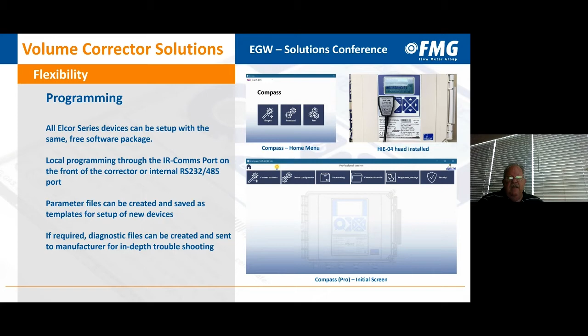Programming. So each corrector, the old ones as well as the new ones today, they require a meter K factor, compressibility calculation method. How are you going to use this with an AGA8, an NX19? Those are all available. At last count, there were 9 different compressibility calculation methods available to use, already pre-programmed. You just go in and pick the one you want. Gas composition, set points of alarms. These are all things that in the past just weren't available. They are now.